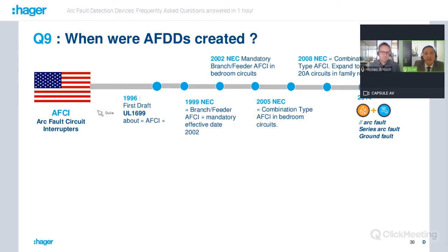So in 1996, the first draft of UL 1699 mentioned AFCI. The first version of the NEC standard in 1999 described and required AFCI as mandatory starting from 2002 in the bedroom circuits. From 2002 to 2008, a lot of evolution was made, and the AFCI types have more combinations and expanded to 20 amp circuits in family rooms.